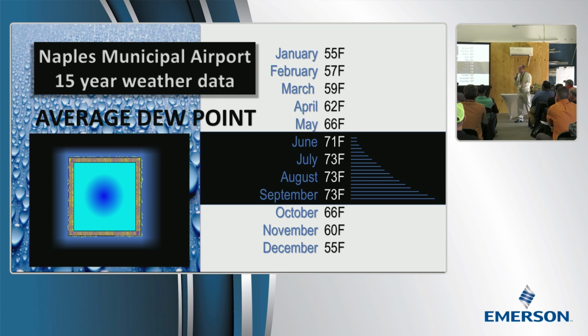Same thing with the duct. If the duct can reach 73 degrees, then you're very likely going to get some condensation, so it should be anticipated. Now, the daily spikes that we record, usually in the early morning hours, we can have an 80-degree dew point. And as a matter of fact, we can have a higher dew point inside an unconditioned space that's filled with fluffy stuff.